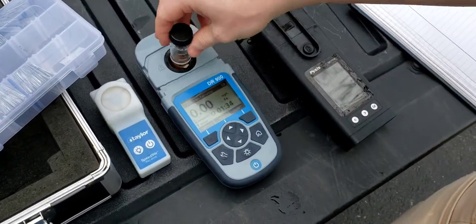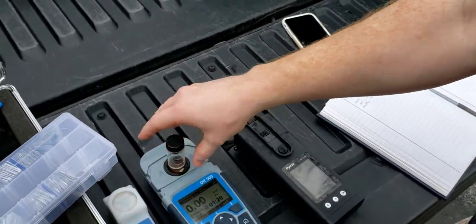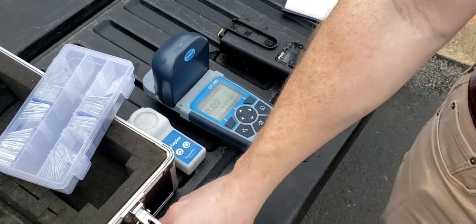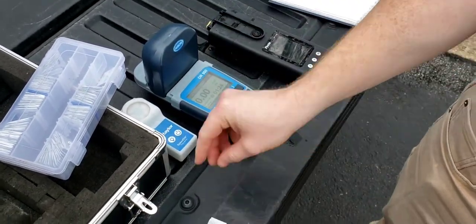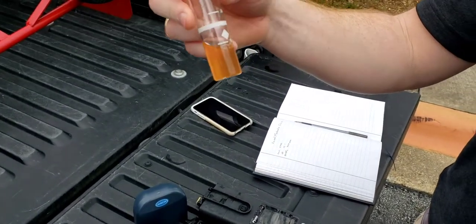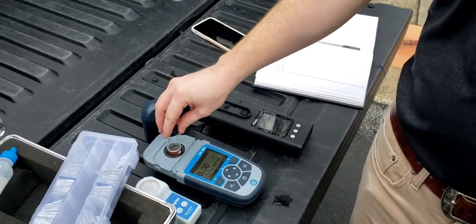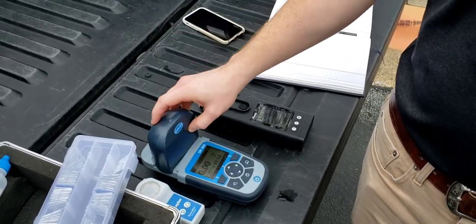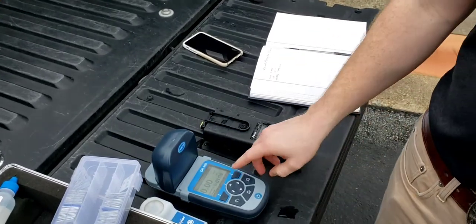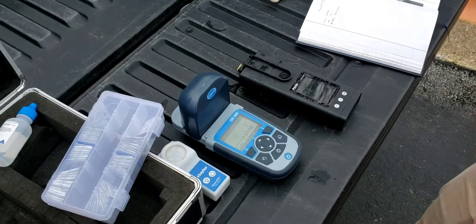We're testing that right now with this Hach DR900. Basically you put a water sample in here, a clean one, and you zero it out. You then add a reagent — I've already done this — and that reagent reacts with the iron in the water. It turns a reddish, orangish color. And when the timer counts down, it reads the difference between the zero water and the colored water, and gives you a total parts per million of iron in the water.